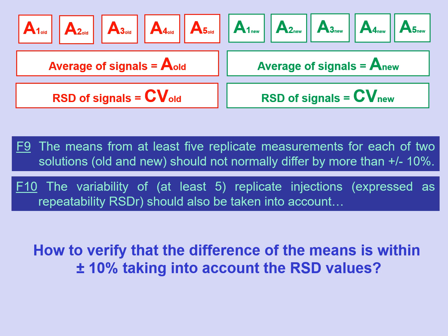With this data, we can calculate the mean values of the responses obtained for each standard — A-old and A-new — and the corresponding values of the coefficients of variation, CV-old and CV-new, and check whether or not they meet the criteria established in points F9 and F10 of the SANTE document. But how can we verify that the relative difference of the mean values is less than 10%, taking into account the values of the coefficients of variation?